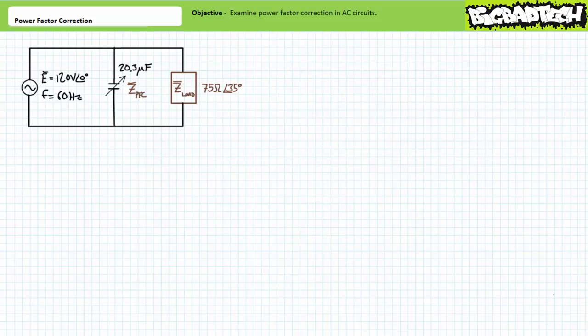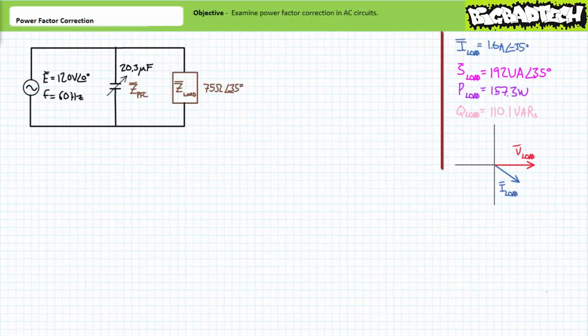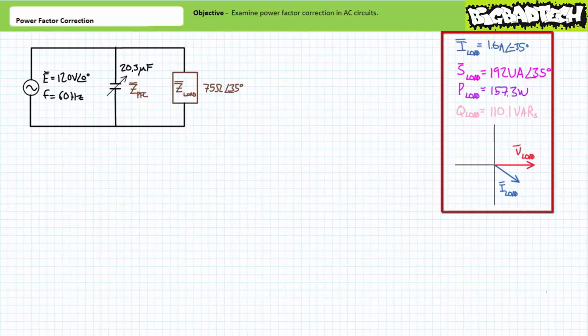Let's now examine how this upgraded system, now including the 20.3 microfarad power factor correcting capacitor in parallel with our electrical load, operates. Both the electrical load and power factor correcting capacitor appear to be perfectly in parallel with the 120 volt 60 Hz AC source. From the electrical load's perspective, nothing has changed because it's still perfectly in parallel with the 120 volt 60 Hz AC source.